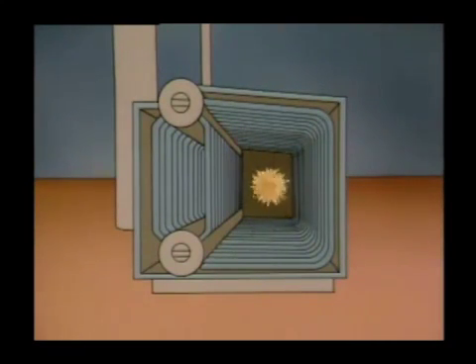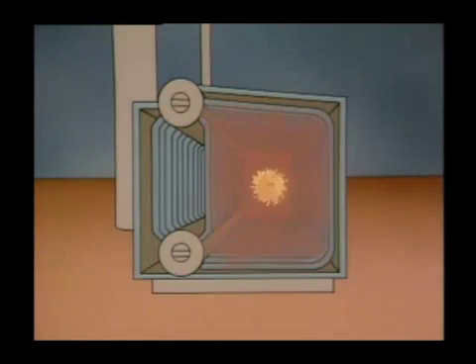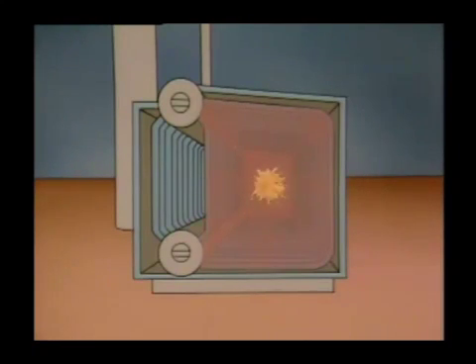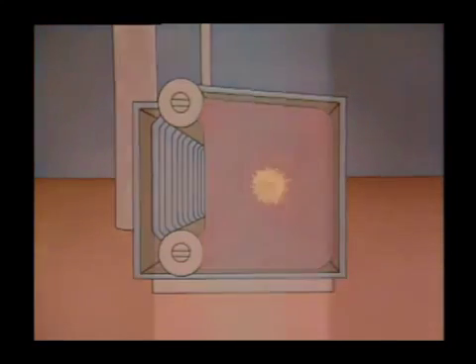The burning fuel also produces combustion gases. As these hot gases pass through the boiler, they transfer heat to the tubes as well — this is convection heat transfer. As the outer surfaces of the tubes absorb heat, conduction heat transfer occurs. Heat is transferred from the outer surface to the cooler inner surface, and then from the inner surface to the water flowing through the tube. Convection heat transfer also occurs as the warmer water mixes with cooler water. When enough heat has been transferred to raise the water temperature to the boiling point, steam is produced.